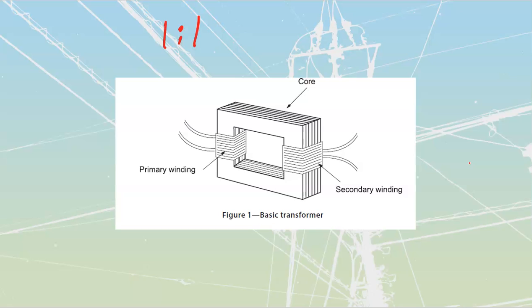In most other cases, though, we are going to have a high voltage and a low voltage winding. Those are identifiable. Now, the high voltage winding does not mean primary winding. This thing could be high voltage or low voltage. Same as my secondary, it could be high voltage or it could be low voltage. Actually, I wanted to reverse that. I'll just call this low voltage or high voltage.